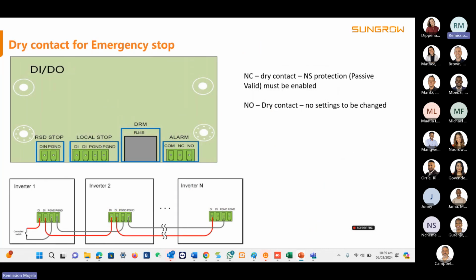And then we have the dry contact for emergency stop. With the dry contact, you can use a normally closed or a normally open dry contact switch. With a normally open dry contact switch, you don't need to change any settings. You can just plug them on the DI, like I've indicated at the bottom. You can connect it on the DI digital input port and just leave it like that. But with the normally closed switch, you have to connect them, then enable the NS protection passive valid. You just have to enable one setting on the system for the dry contact emergency stop to work. But you can use either a normally closed switch or a normally open switch.